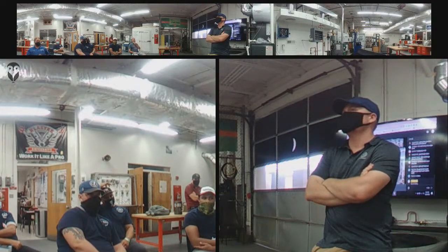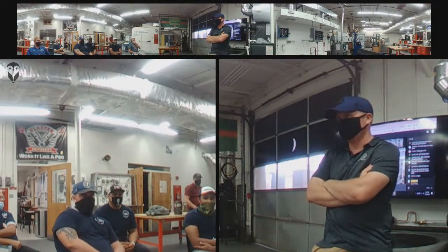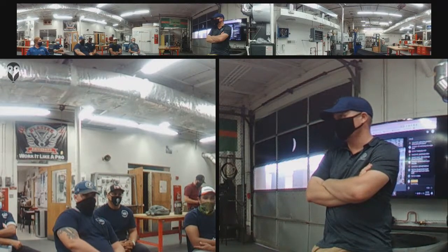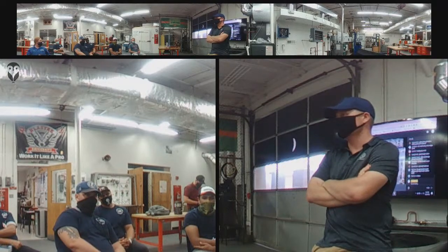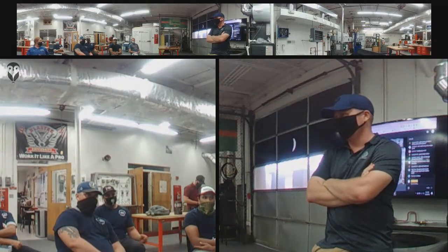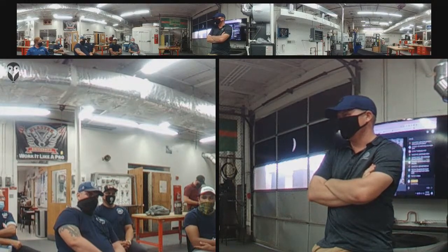Okay, so on that relay, I would want to understand what that relay does. What's the purpose of that relay? Do you know? Yeah, for the fan. For the blower or for the condenser fan? For the blower, yes. And so you had 24 volts applied to the coil, but the contacts weren't consistently making. Is that what you're saying? Yeah, it's a little confusing.